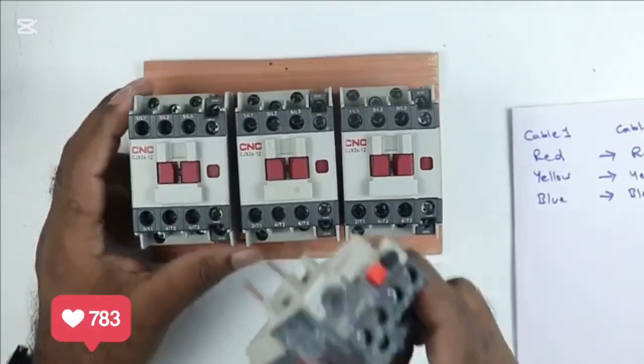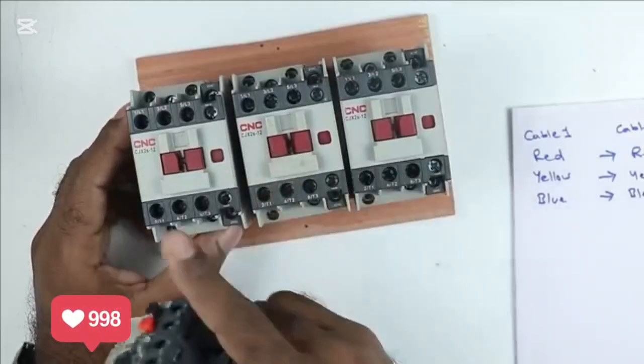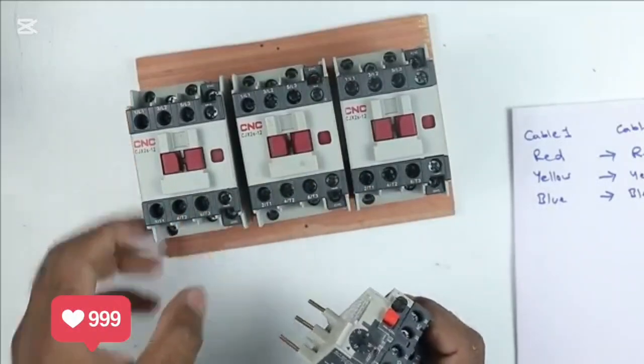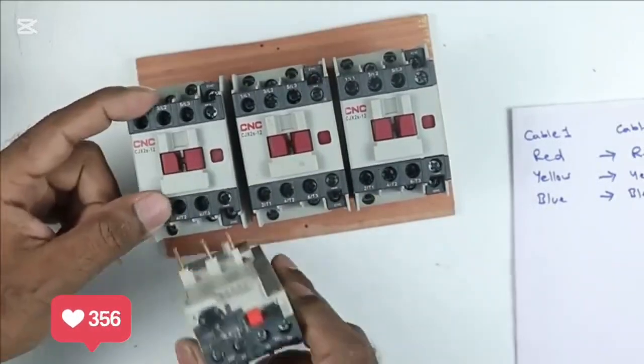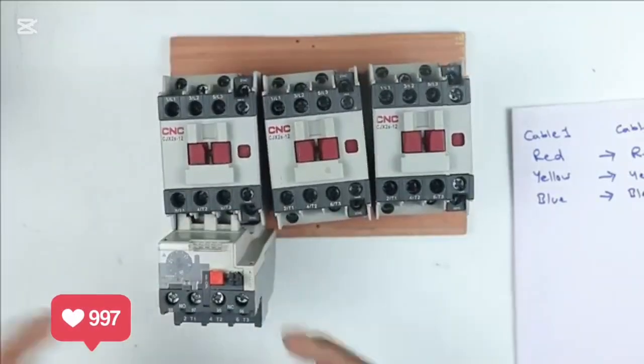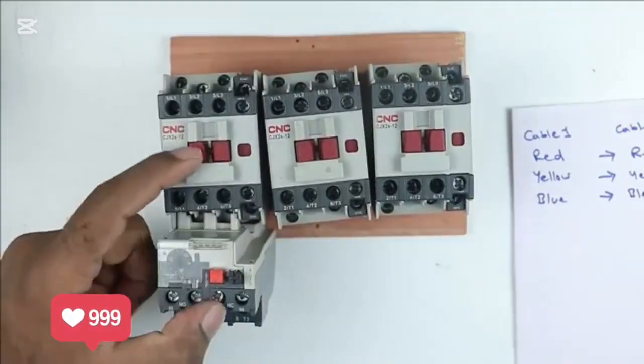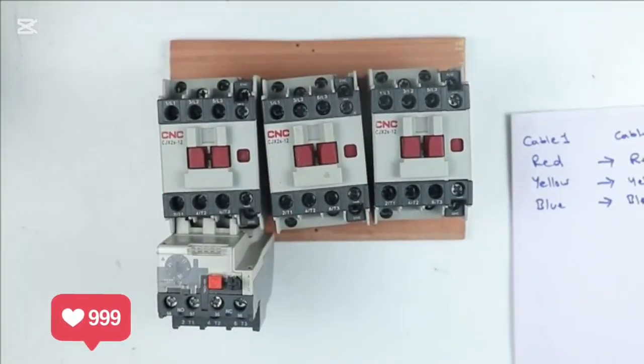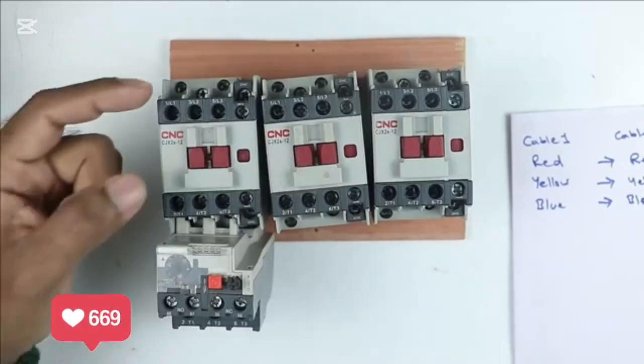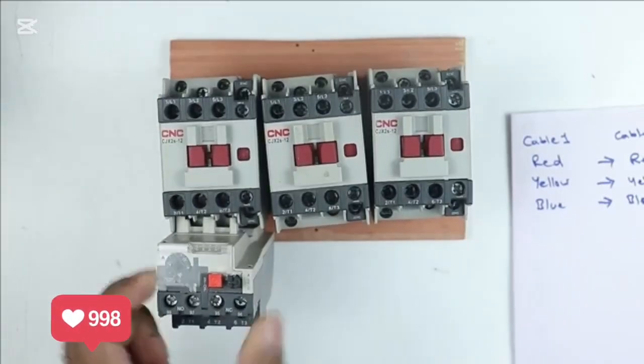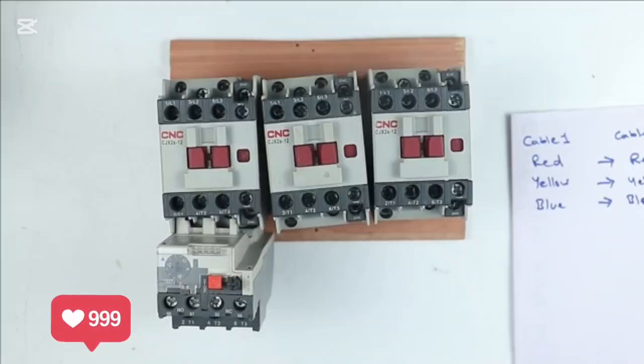Here the overload relay will be connected with any one contactor. What I will do is connect the overload relay to the first contactor. The contactor to which the overload relay is connected is our main contactor. You should keep one thing in mind: the contactor at which the overload relay is connected will be our main contactor.